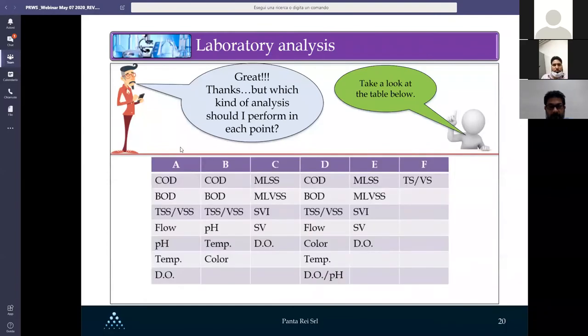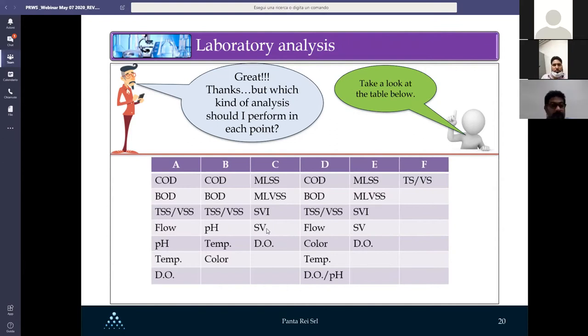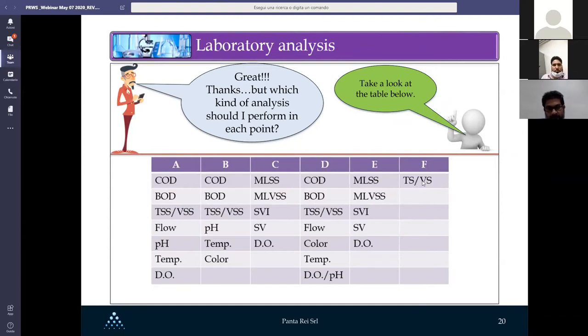Looking at the analysis table: at the inlet, common parameters are COD, BOD, solids, flow, pH, and temperature. Inside the oxidation tank, we need to know the quantity of biomass, the sludge volume measured by Imhoff cone, and the SVI (sludge volume index). The same parameters apply at the outlet. For sludge return, it is important to understand biomass composition, and for waste sludge we measure total solids and volatile solids.